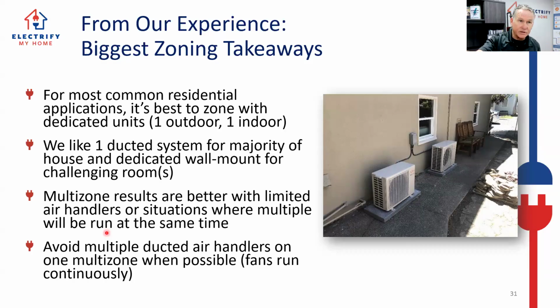I think you get a copy of these slides. I don't care if you use that little graph, but show them what the benefits of two smaller systems are. I've got redundancy. If one unit goes down, the whole house isn't down. I've got a lower modulation rate on each system, and I've got smaller systems that cost less to install. And those systems, when they're running at that ultra low modulation rate, are using a fraction of the watts. So it's going to cost more to install this, but it's going to cost so much less to live with over the next 20 years that it's going to more than pay for the additional investment.